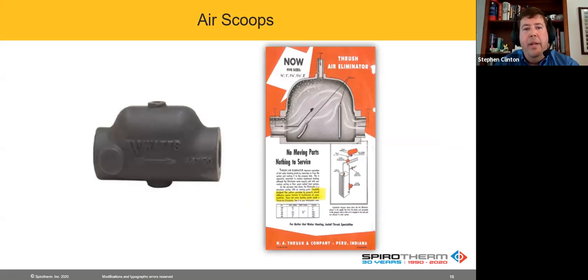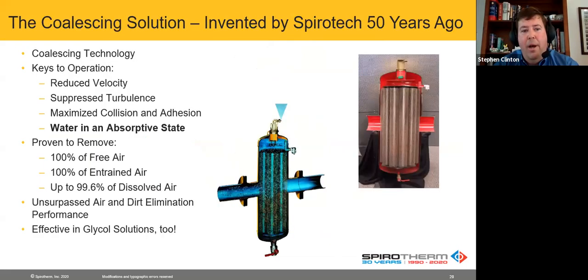So yes, someone had asked about the air scoop. That's an air scoop that's been in the industry for a while. So basically, we're doing the same thing. We are removing the air. We can remove 100% of the free air, pockets throughout the system, all the entrained air, up to 99.6% of the dissolved air.